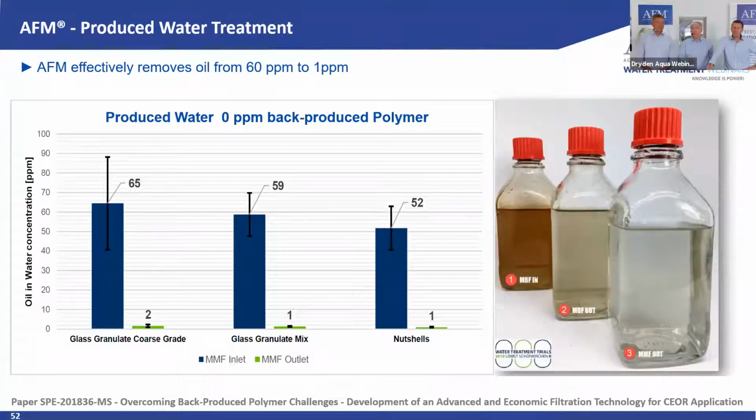Nutshells are much better in this application. That's why there is no sand used in this. That's why they use nutshell filters worldwide for the removal. You can see the performance is quite good with nutshells, but we already exceed the performance, or let's say we can say it's very similar to the nutshell, especially in this produced water application.